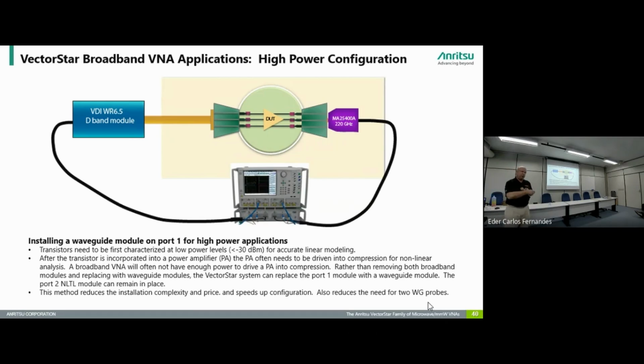So we can support, in addition to what I've shown you already in terms of configurations, a hybrid configuration with one of the Anritsu modules here. This is the 220 module with the probe. And over here is the VDI module with a waveguide probe. Now, this is not a broadband system, but in many cases for these nonlinear measurements, they're not broadband. They're in a specific band, like D or G, something like that.